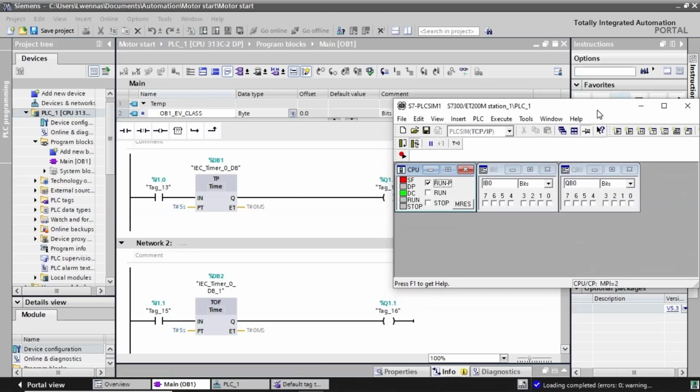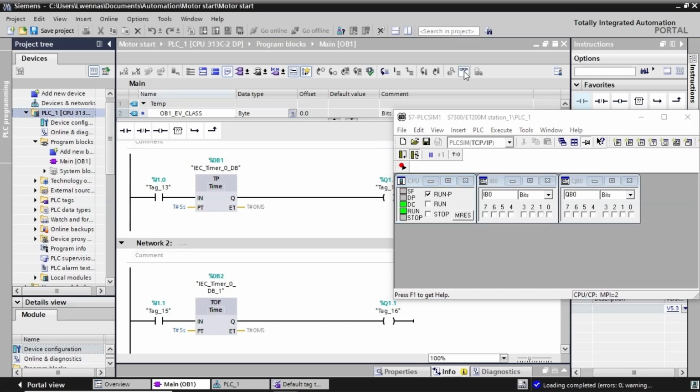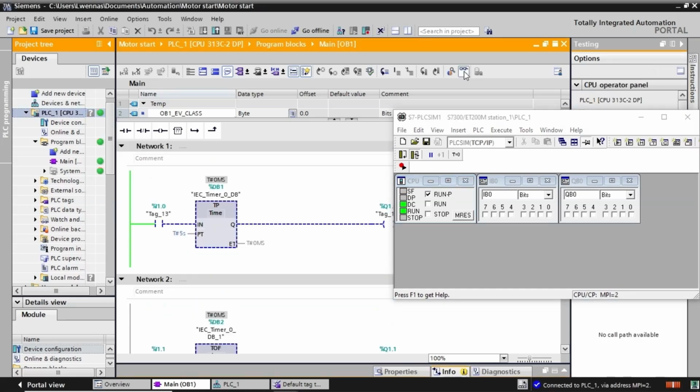We launch PLC Sim and start simulating the timers one by one. We used the byte number 1 for the addresses. Therefore in here, we modify the byte number for both the input and output, then we put the ones we used for this example. By clicking on the first input, the timing starts and the timer's output turns on and stays active until the preset time, PT, is up.